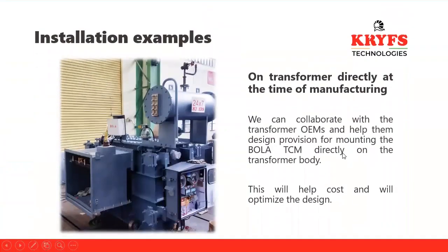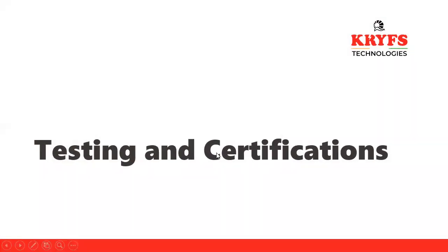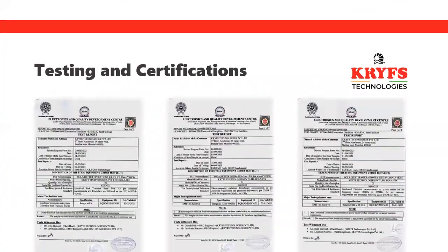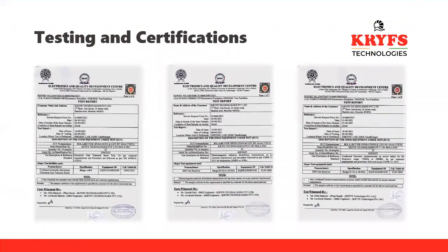Normally, it is always good to have the BOLA TCM system installed in a new transformer. We can collaborate with the OEMs, and the OEM can make a special provision on the transformer itself to install the BOLA device. These are the 3 installation examples I have shown; there can be many, depending on site requirements. The BOLA system is type tested in all the electrical, mechanical, and other required testing, so we can easily participate in tenders with all these test certificates.